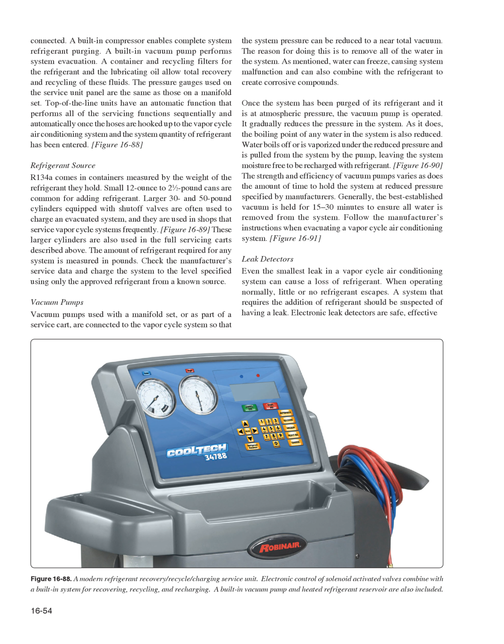Vacuum pumps used with a manifold set, or as part of a service cart, are connected to the vapor cycle system so that the system pressure can be reduced to a near total vacuum. The reason for doing this is to remove all of the water in the system. As mentioned, water can freeze, causing system malfunction, and can also combine with the refrigerant to create corrosive compounds.